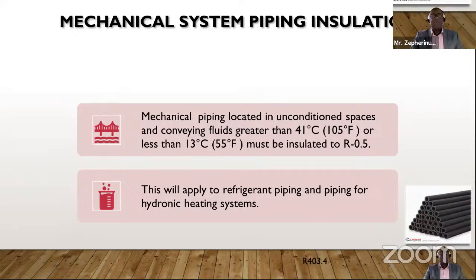The mechanical systems, the code makes provisions for insulation. As you can see on the bottom right, the mechanical piping located in unconditioned spaces and conveying fluids that are greater than 41 degrees Celsius or less than 13 degrees Celsius must be insulated to R0.5. This is an example of the requirements for mechanical systems as it comes to insulation, the R value, the thermal resistance of that insulation for mechanical systems.